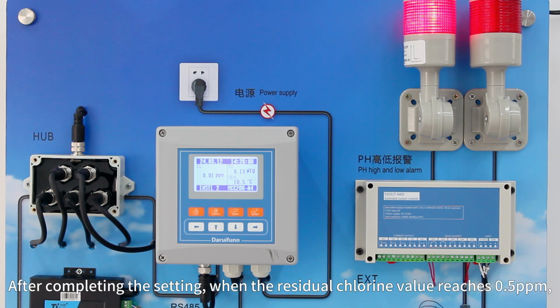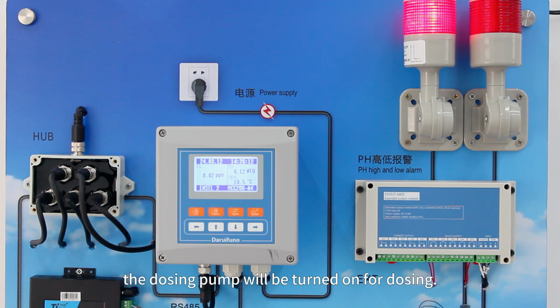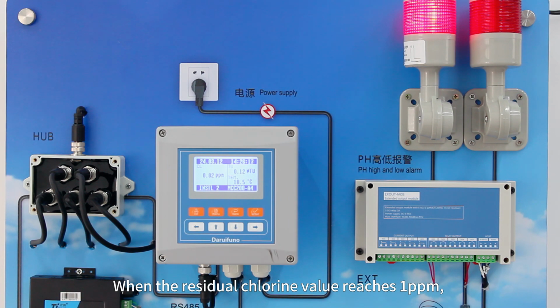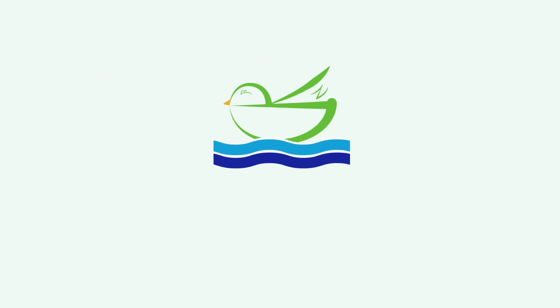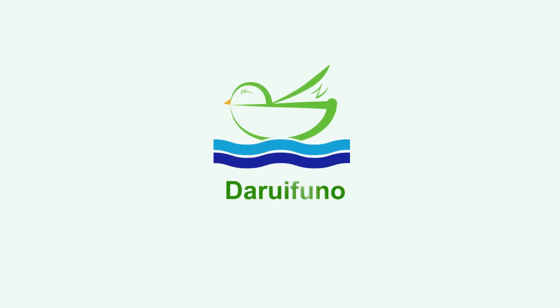After completing the setting, when the residual chlorine value reaches 0.5 ppm, the dosing pump will be turned on for dosing. When the residual chlorine value reaches 1 ppm, the dosing pump will turn off the dosing. For more information about the functions of expansion modules, please contact us.